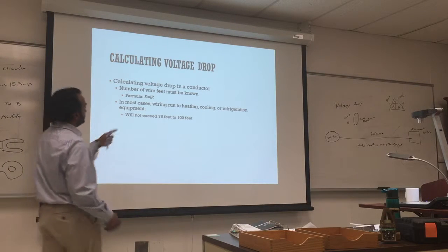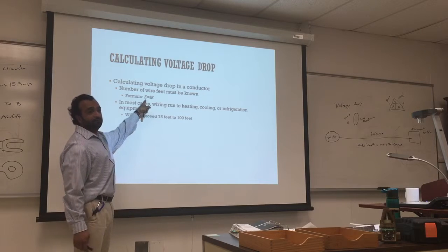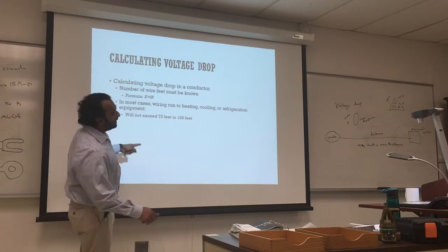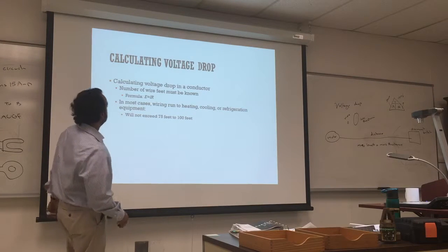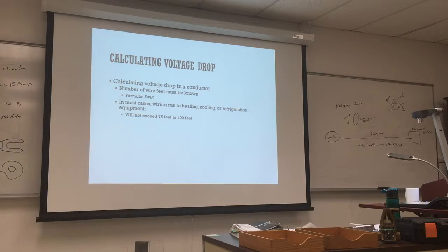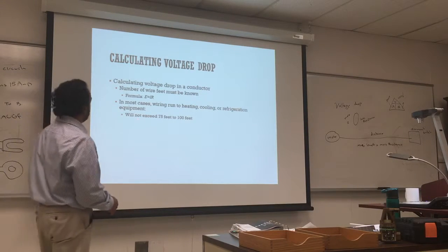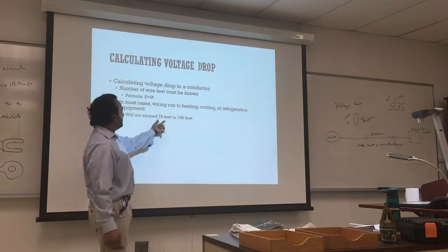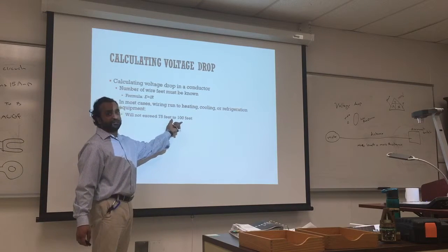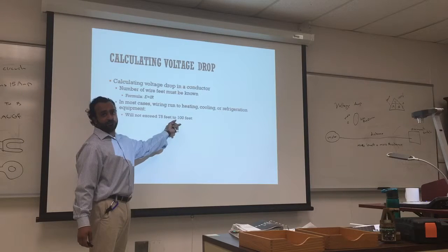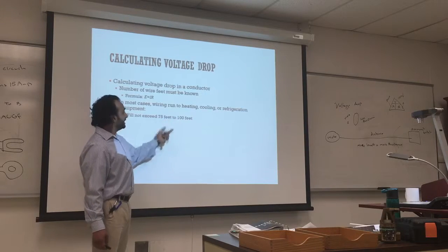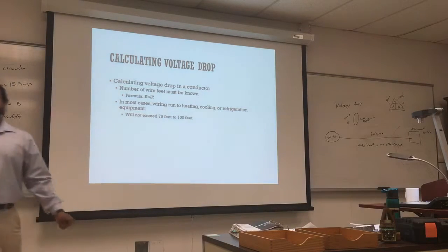Calculating voltage drop is the same thing. The formula: voltage equals amperage times resistance. In most wiring runs to heat and cool refrigeration equipment, it will not exceed 75 to 100 feet. I've seen 100 yards as the general rule now with 14 gauge. But if you have to, you calculate.